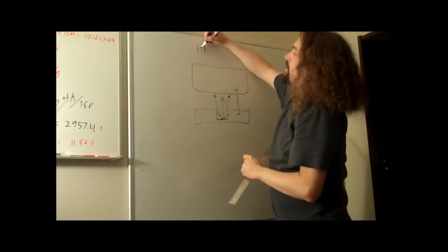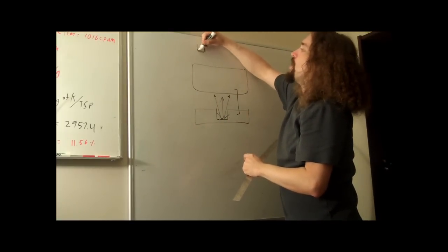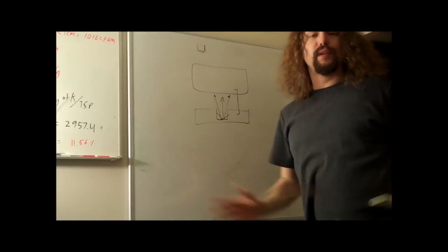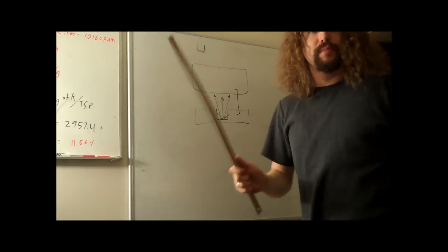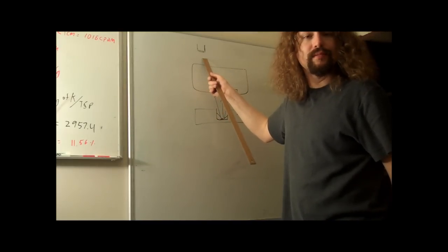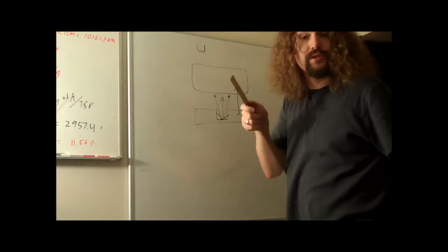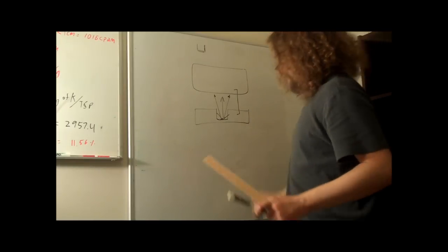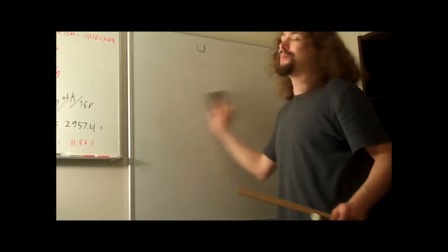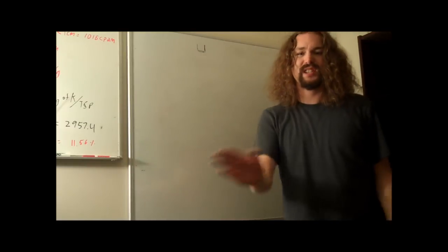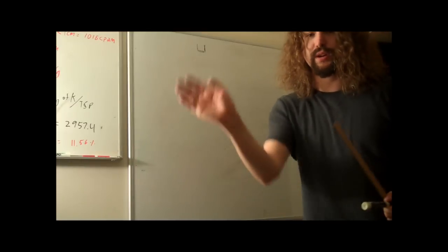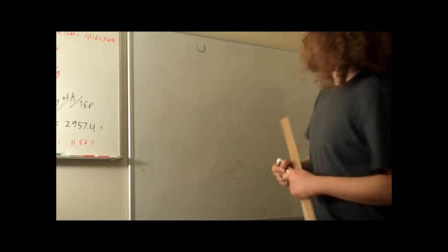This right here represents the total distance in regular temperature air, room temperature that I have right now, at this altitude and pressure. This is how far the alpha particles can go from my Geiger counter. I can take my Geiger counter and show you that this is true. I calculated this mathematically. It goes beyond the scope of what we're doing here because most people aren't going to be calibrating for an alpha source, and this is something you mostly are going to have to do for an alpha source. So I'll just show you for giggles, but don't worry about this being part of the calibration.